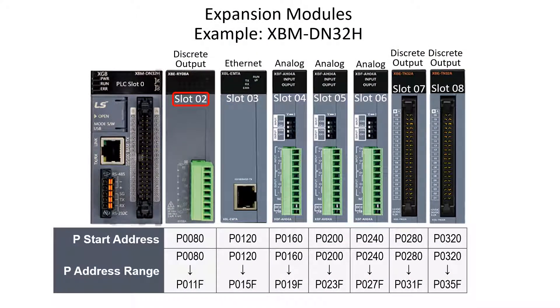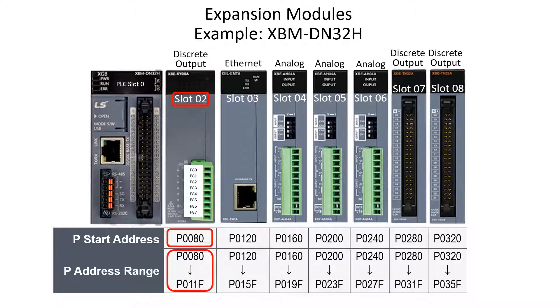Slot 2 is the first expansion slot in the M-type configuration. The first discrete address is P-Word 8 bit 0, and the range is P8 bit 0 through P11 bit F. The last character in the P address is the bit in hexadecimal format. In the configuration shown with an 8-point relay module in slot 2, the discrete bit addresses are P-Word 8 bit 0 through P8 bit 7.